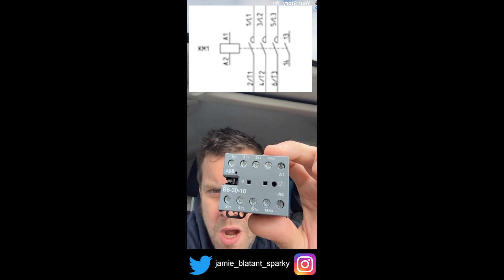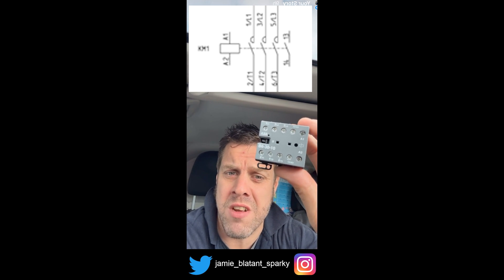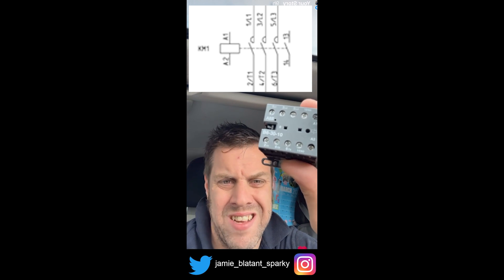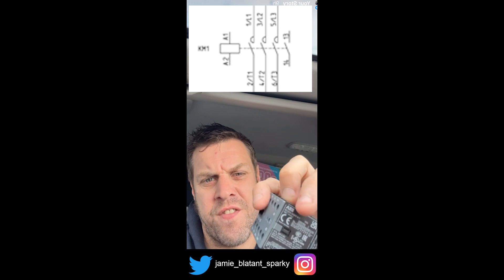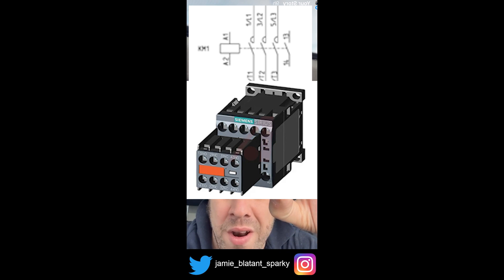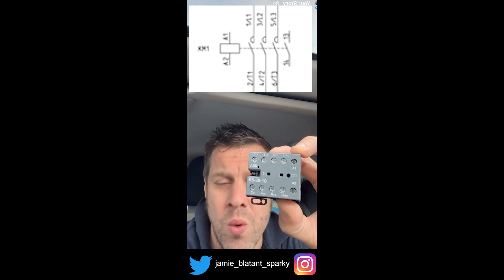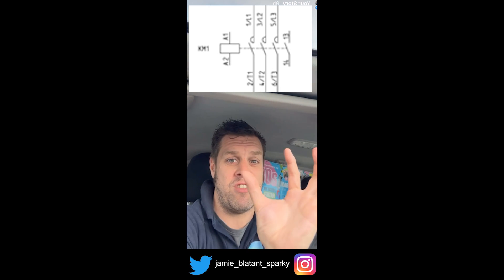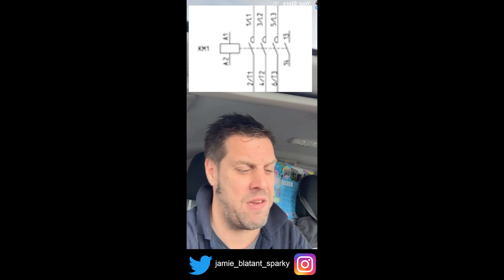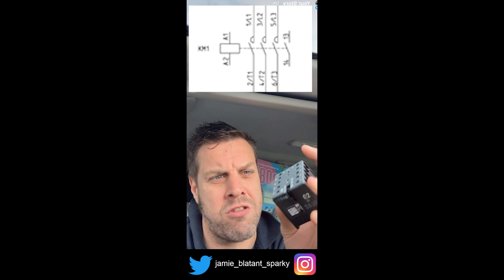The only other thing you've got on there is a normally open contact, which enables you to use it as what they call a DOL starter — that's the most common contact you require. If you require more contacts — for example, you want a normally open contact that tells you if the contactor is in or out — you can stick a thing on the front called an auxiliary block, which gives you more control contacts. You've got your L1, L2, L3 power contacts, your NO control contact, and your coil which pulls it in. Energise the coil — contact closes. De-energise the coil — contact opens on spring return. You may need to know if it's on or off — you put auxiliary blocks on top for that.